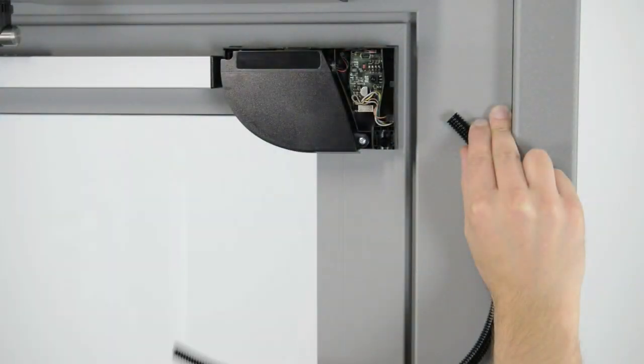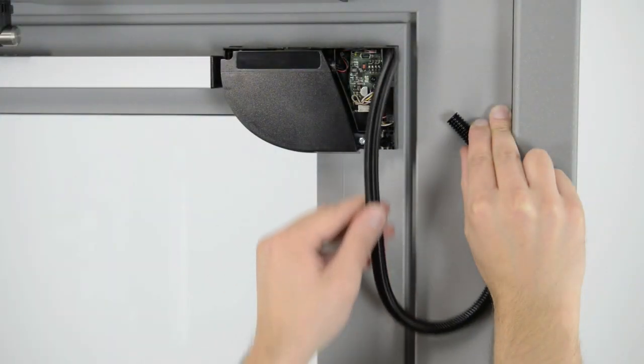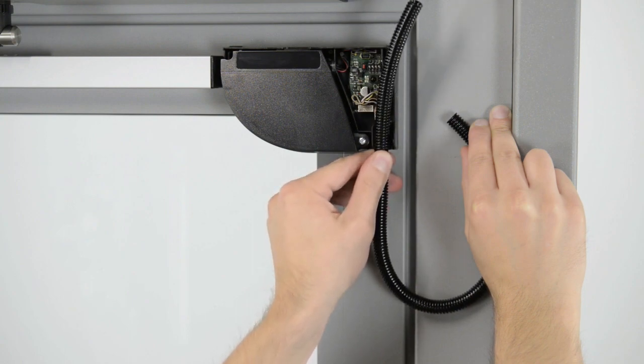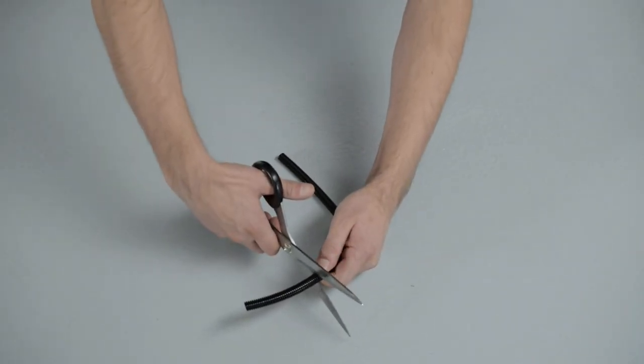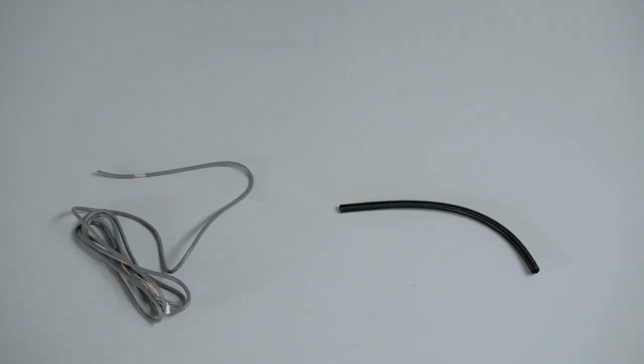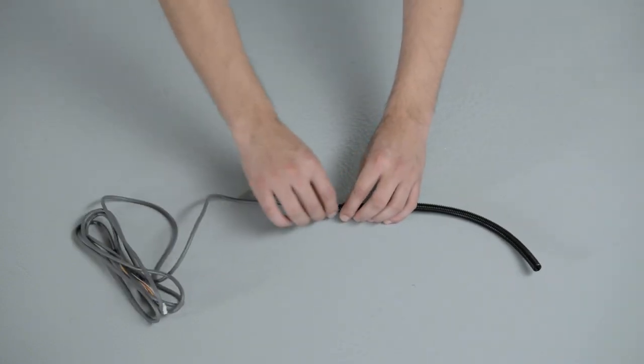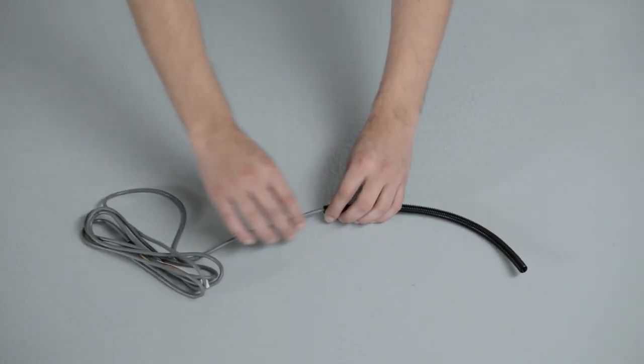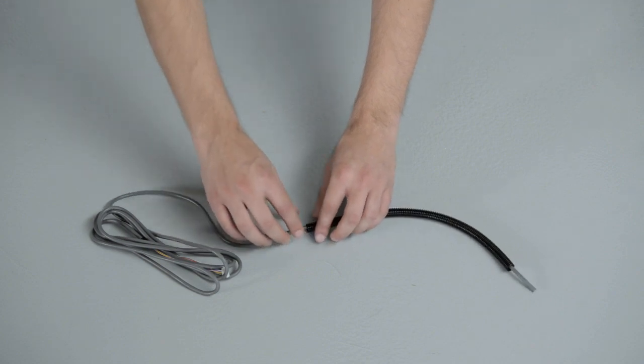Take the flexible tube and determine how long it should be in order to reach the door controller. Cut the surplus to avoid undesired detections caused by the flexible tube. Pass the power cable through the flexible tube. Connect the white plug to the white connector.